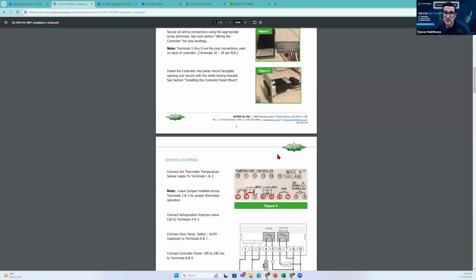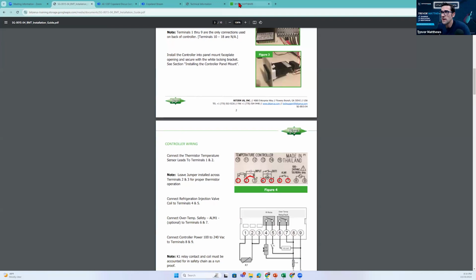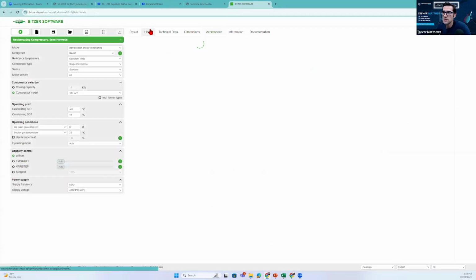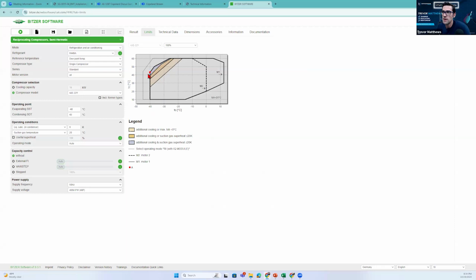This here explains how you do it. So for an example, if someone asked me the question, would I use liquid injection? If I'm running my compressor right up here, select operation mode RI. So that's refrigerant injection. So right here, this compressor could go, and I didn't point that out first. If I'm running anywhere out here, I can go lower than that minus 40. I can go down to, what did it just say here? Minus 45 with the RI module. So let me do minus 45. Let's see, it should come up this time.